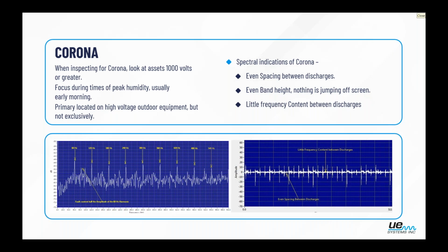Typically, we like to see that 60 hertz line frequency, so power distribution going out at 60 hertz. We should see, as in this left image, 60 hertz line frequency showing up consistently through. Not much content between all of them. And then on the event over time, typically we will see the discharge on the negative cycle, fairly even band height and spacing, and really not a whole lot of chatter or noise in between each discharge. So it's a fairly consistent, easy to read breakdown of that sound.